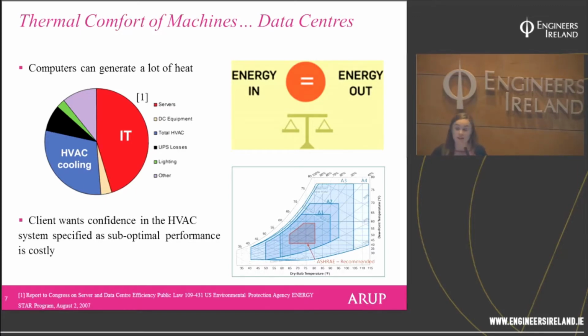Typically, data centers are designed based on an energy in, energy out approach: we know how much heat is generated, and therefore how much we need to cool it down. But there's a lot of room for error, and the operating conditions for temperature and humidity in data centers are quite strict per ASHRAE codes. Our client wants confidence that the data center and the specified HVAC system will perform optimally.